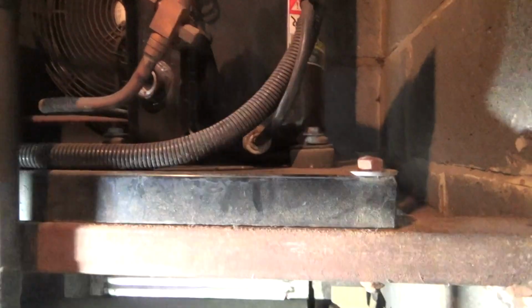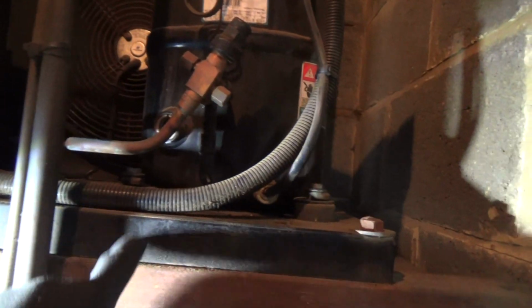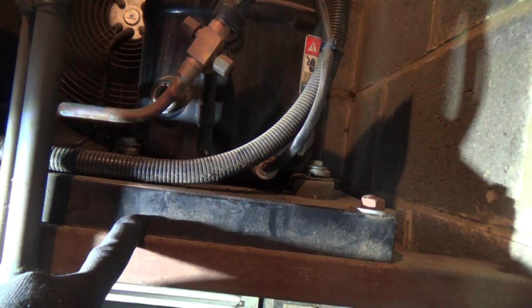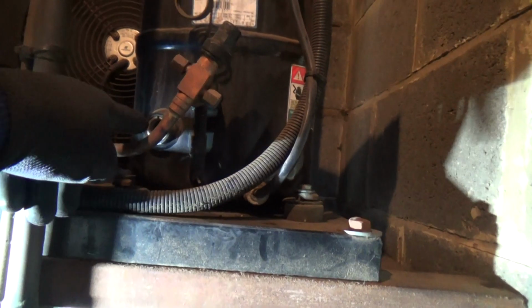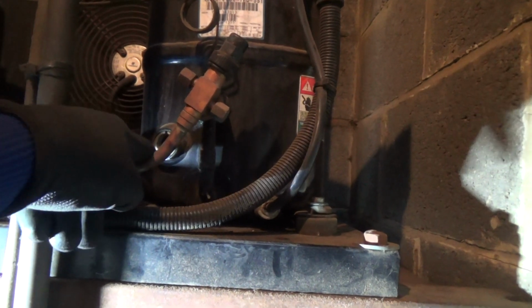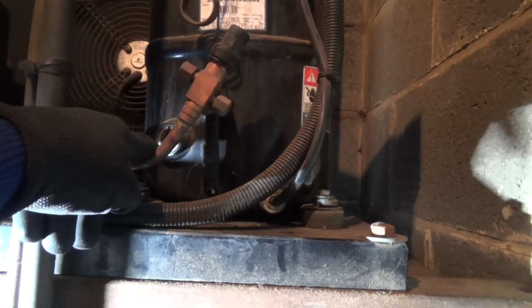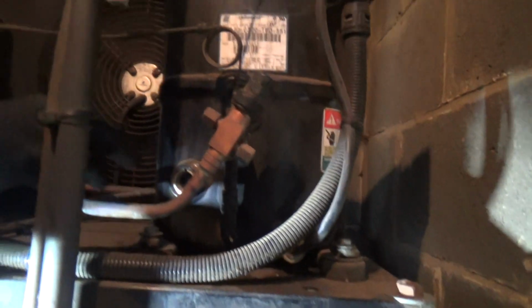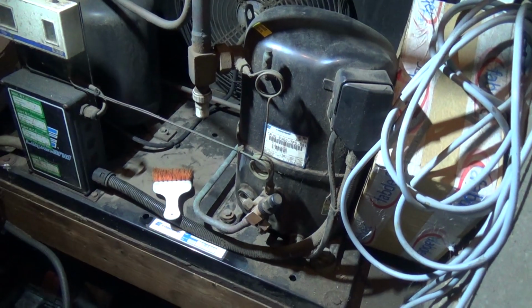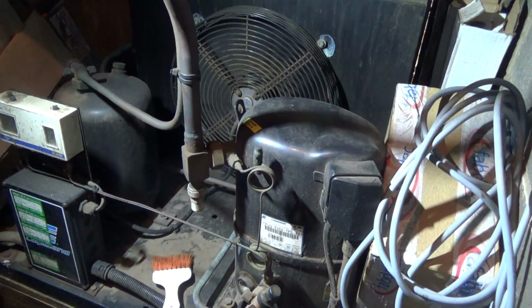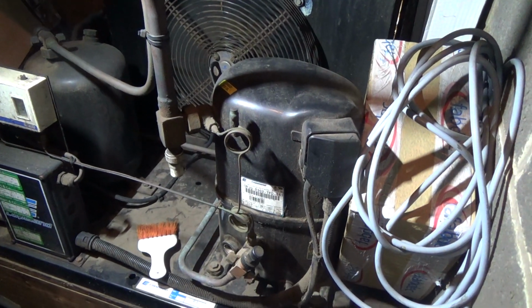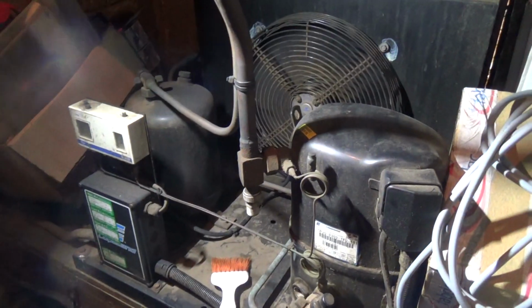It's still on R22. A few years back, before we weren't allowed to work on them, they had the oil sight glasses leak, so they've been changed. That's something that does go on these, you see how rigs go, something to keep an eye out for. But yeah, going well really for original contactors, everything.